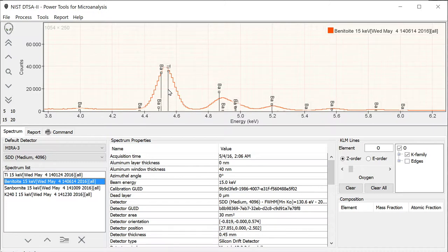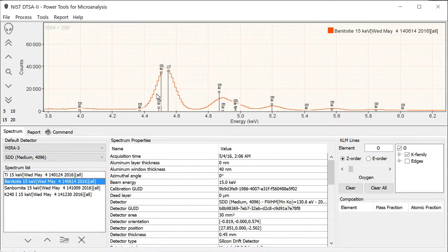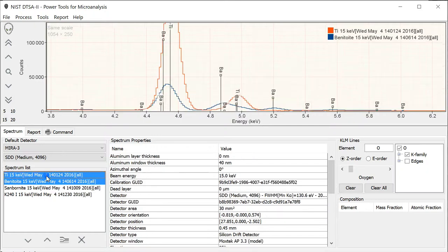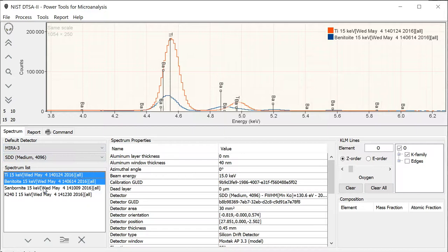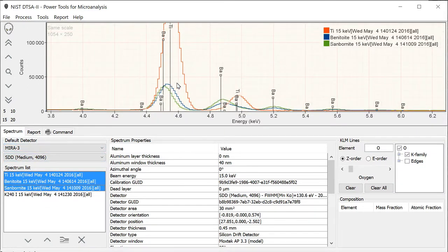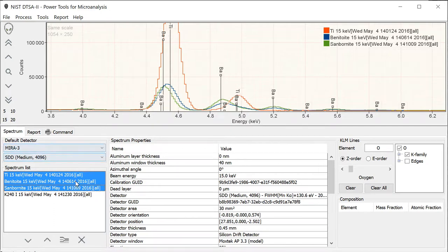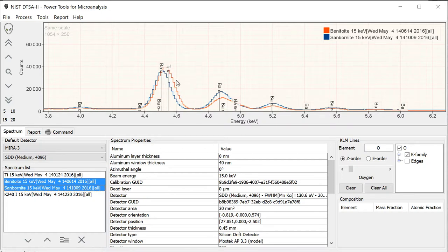To extract the information about the barium intensity and the titanium intensity is challenging. If we were to try and do this by eye, we would probably just give up. But the fact of the matter is, we can fit a pure titanium spectrum and a barium spectrum without any interferences in this region to this peak shape, and we can extract very precisely and accurately the information about how much intensity is barium and how much is titanium. The green spectrum is now a material called sanbornite, which is a barium silicate.